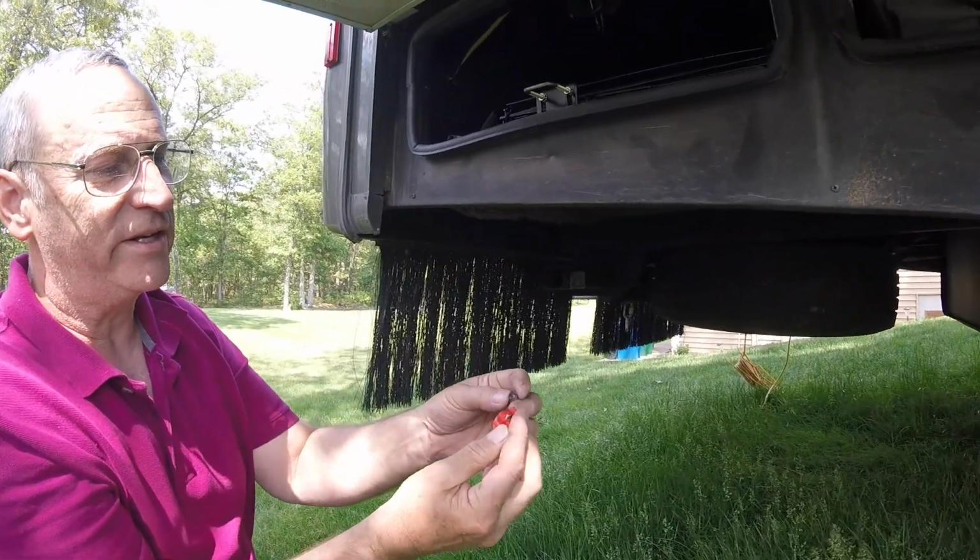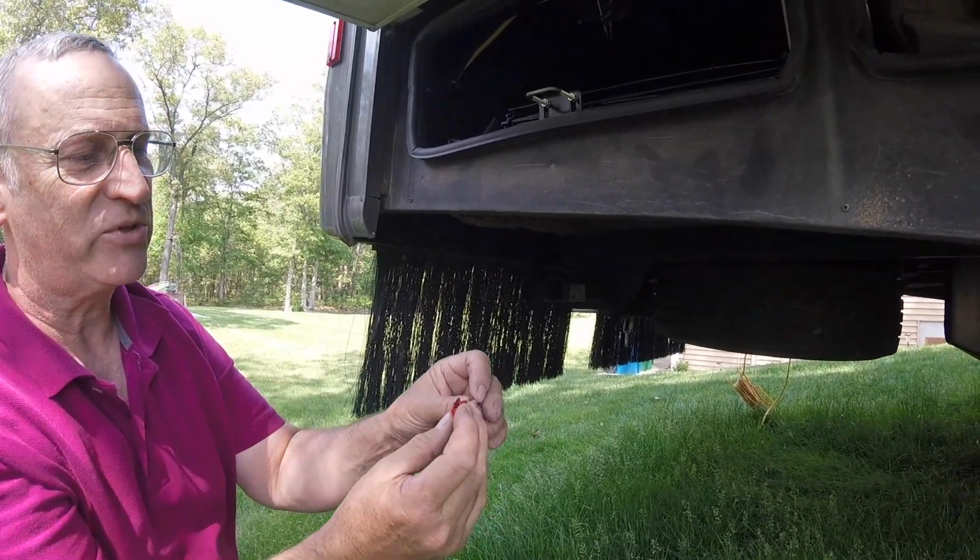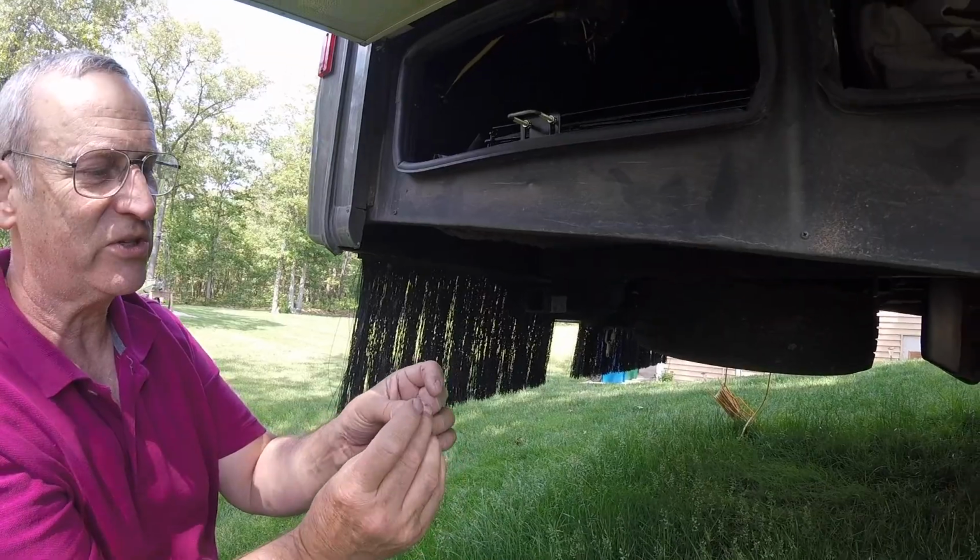It melted the whole wire nut. So luckily that was all it did, and lost connection, so that was a good thing. That's crazy. I'm glad there wasn't a fire started or something. That's pretty awesome. I hope this is it. It turns out that was the issue. It was not at all what I was expecting. A bad connection in that cap, it just totally melted it.